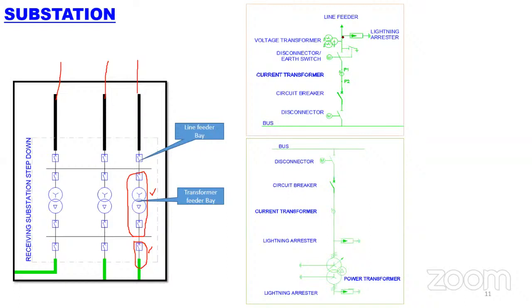Our second phenomenon is a natural phenomenon: if there is a lightning strike on the transmission line outside of the station, traveling waves reach your substation. So what is the prime thing? We need to stop these surges getting into the station. It is a nuisance. For those surges, you need to bypass them into the earth. So the first component we are using is a lightning arrestor, which helps to bypass all the surges into the ground. Then number 2 is a voltage transformer.